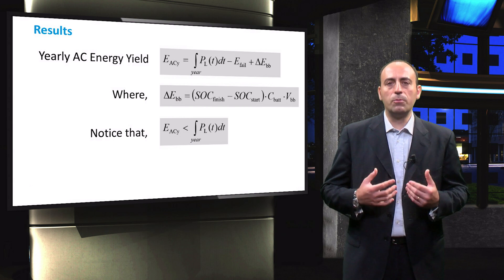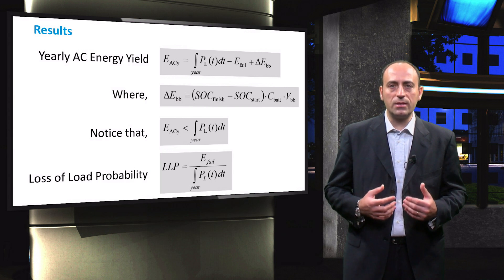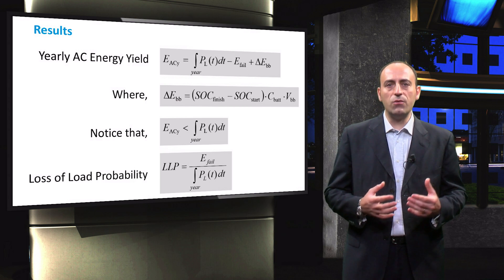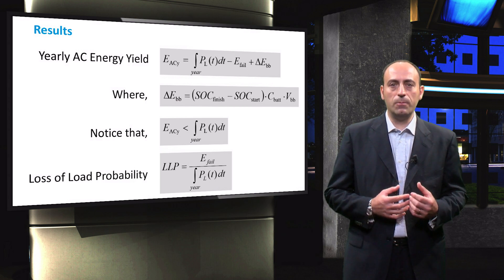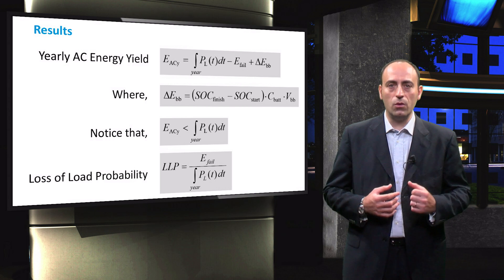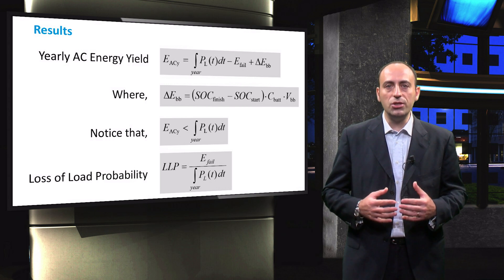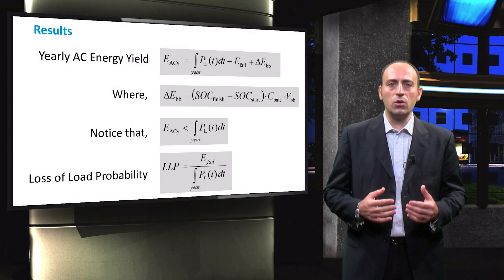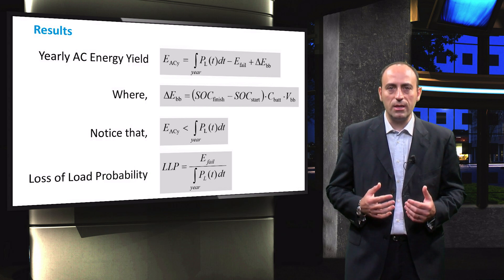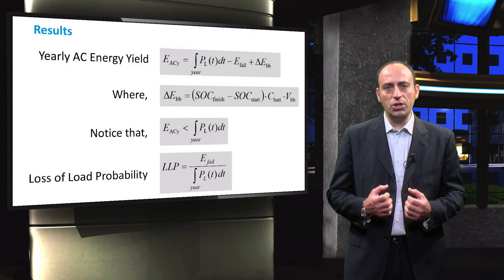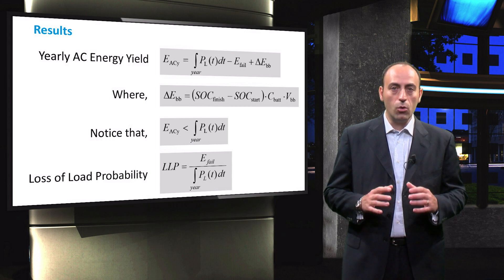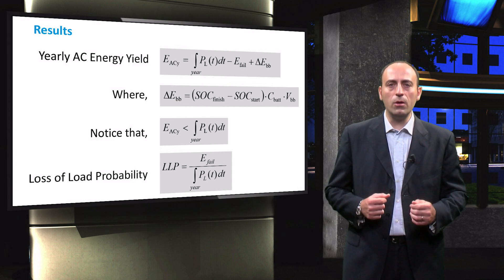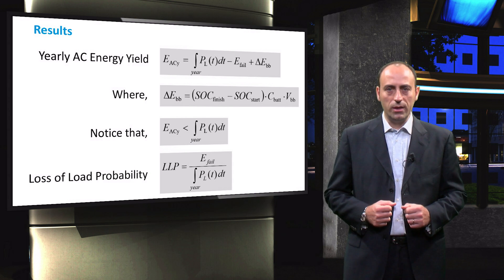Also, from the above expression, we can see that due to the fact that E-fail is a positive value, the AC energy delivered by the PV system is always lower than the total energy demanded by the loads. Thus, the loss of load probability for the PV system is calculated next. It is defined as the ratio between the energy that the PV system fails to deliver to the loads and the total energy requirement of the loads. By calculating the value of loss of load probability for the PV system, the level of autonomy achieved can be analyzed. Moreover, the PV system design can be evaluated before approval by looking at the calculated loss of load probability.